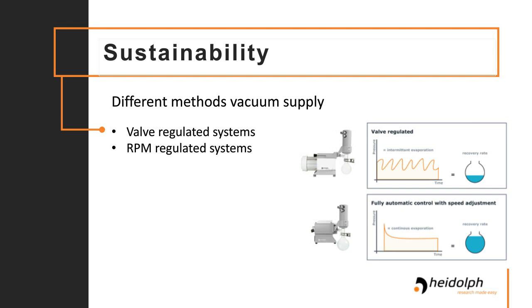The RPM-regulated system is honestly the more up-to-date version of the pumps. The main difference is that the valve-regulated system lets the pump run at 100% all the time, while the RPM-regulated system is, on the one hand, more accurate and is only active as long as you need the vacuum. So as soon as your system hits the set vacuum, it would turn off the pump.